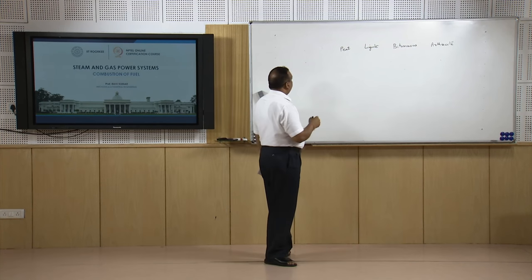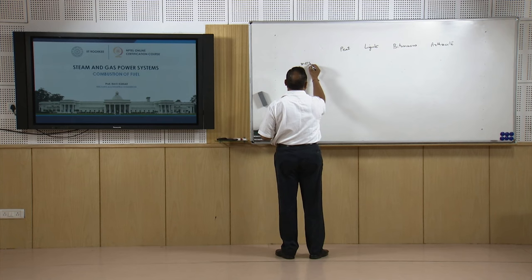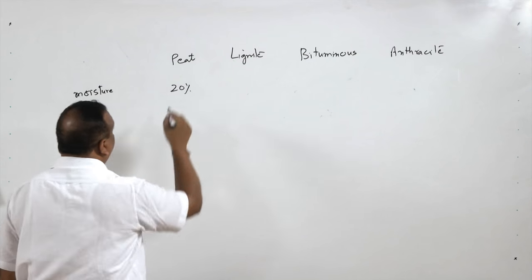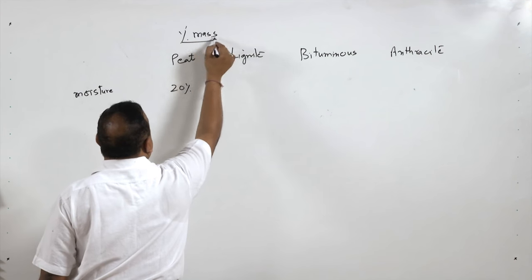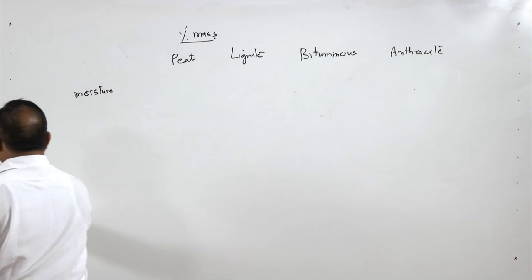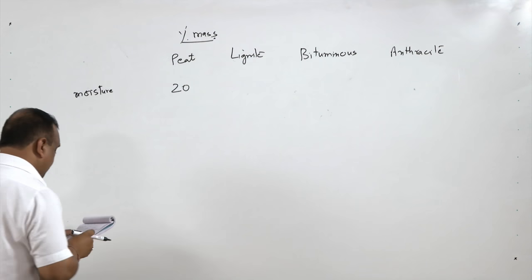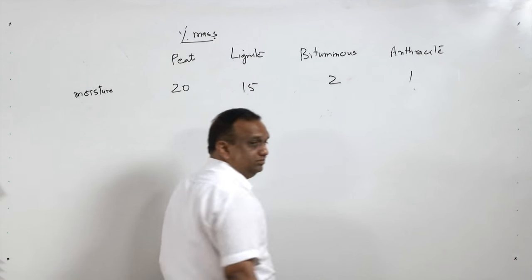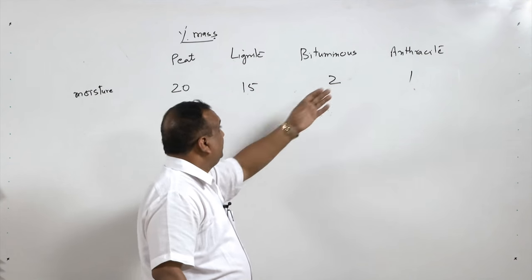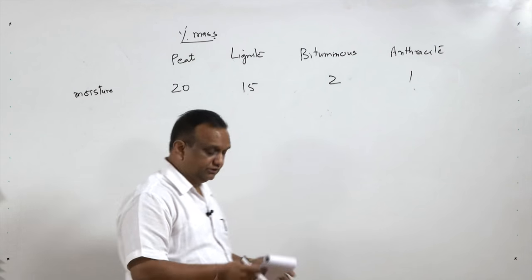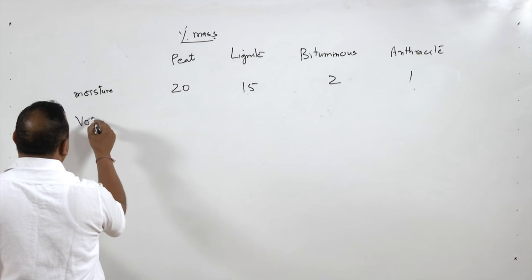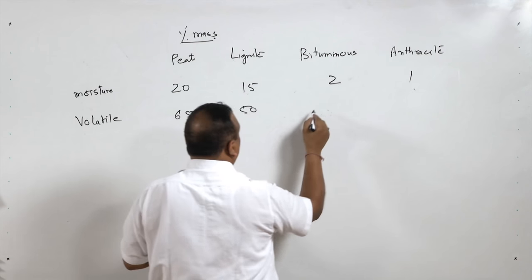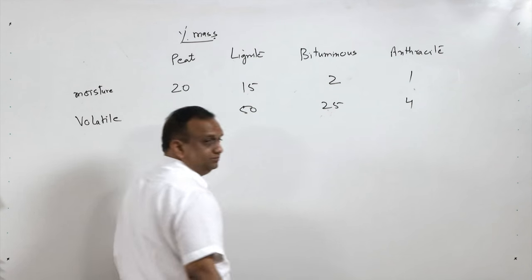Let us take the case of moisture, in percentage by mass. Peat coal has approximately 20 percent moisture, lignite 15 percent, bituminous 2 percent, anthracite 1 percent — almost dry. For volatile material: peat 65 percent, lignite 50 percent, bituminous 25 percent, and anthracite only 4 percent.